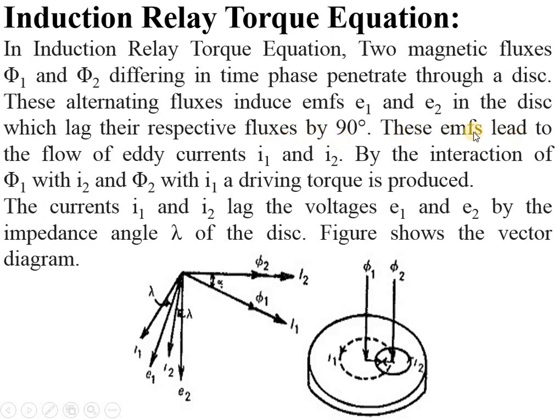These alternating fluxes induce EMF e1 and e2 in the disc which lag their respective fluxes by 90 degrees. These EMFs lead to the flow of eddy currents i1 and i2. By the interaction of φ1 with i2 and φ2 with i1, a driving torque is produced.